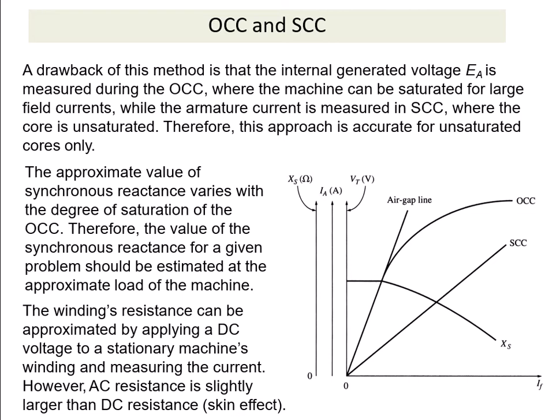So the approximate value of synchronous reactance varies with the degree of saturation of the OCC. Therefore, the value of synchronous reactance for a given problem should be estimated at the approximate load of the machine.